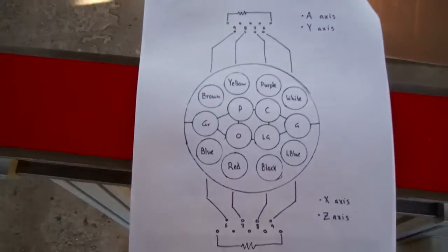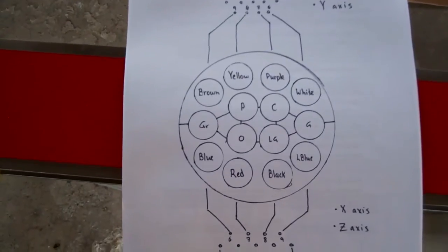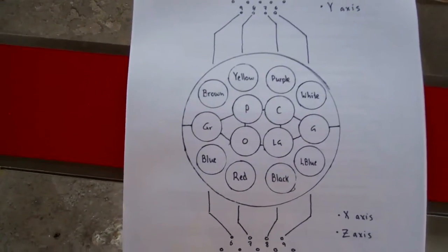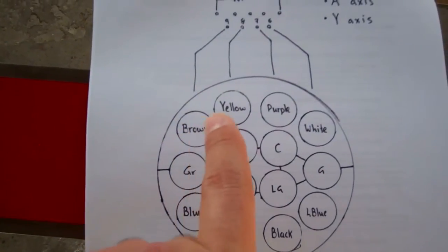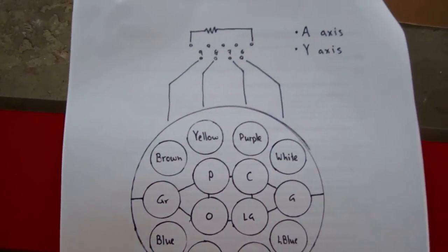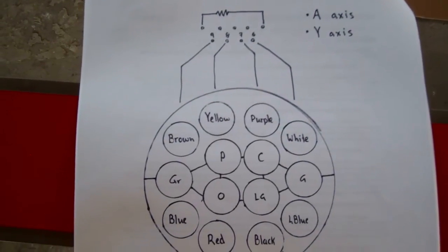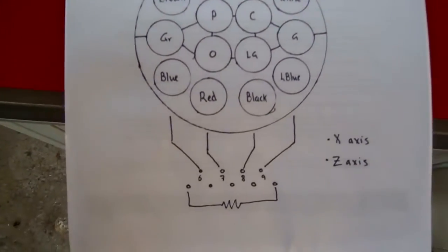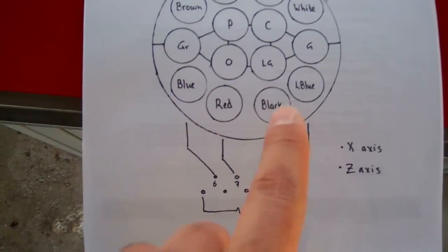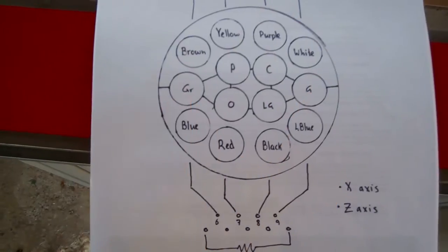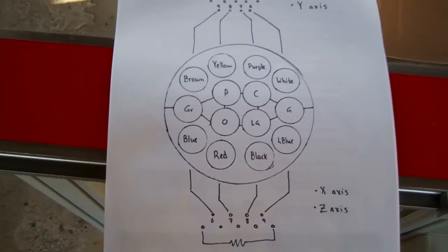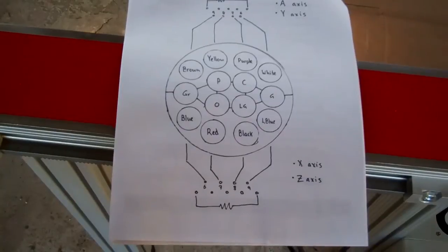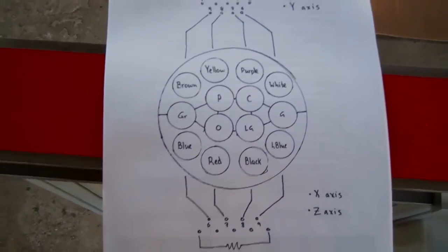You can see here a diagram cross-section of that cable. I've taken four conductors and designated those to one motor or axis, then taken four on the other side for the other one, and all the ones in between are grounded out to the shield. Hopefully that'll provide enough shielding that they won't crosstalk.